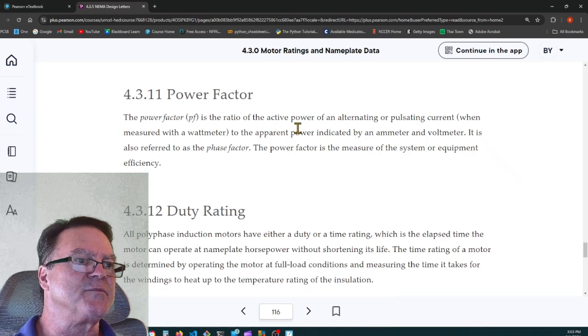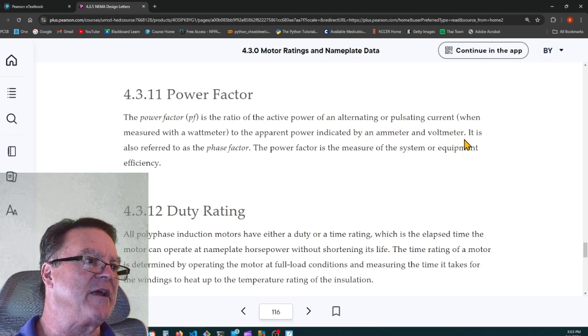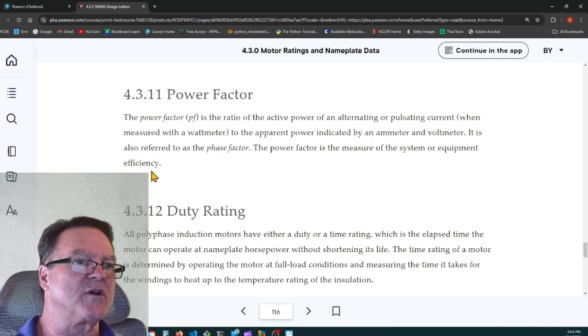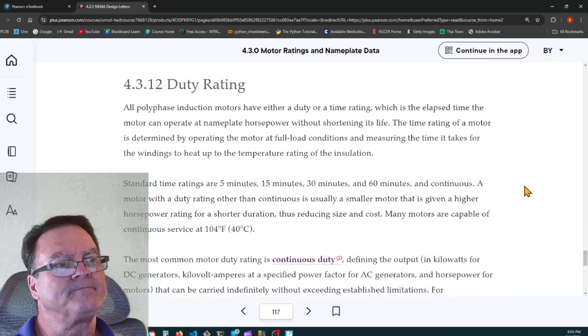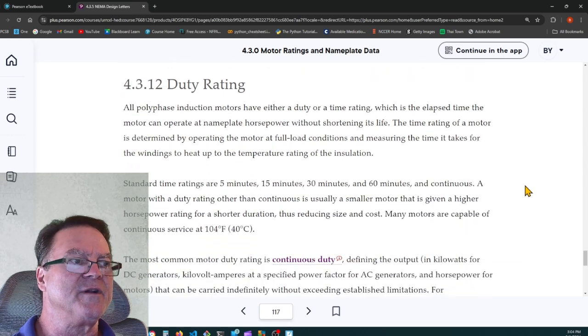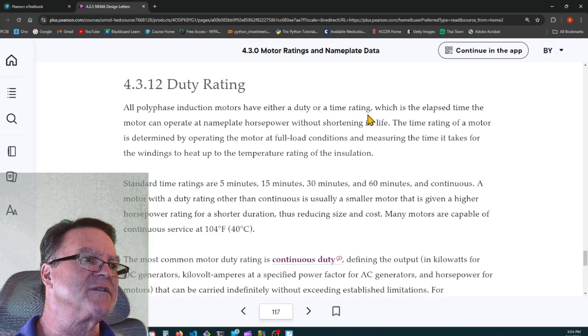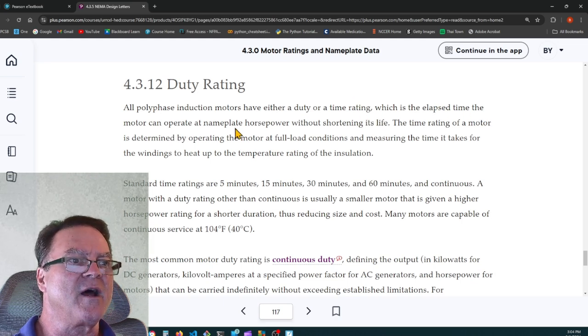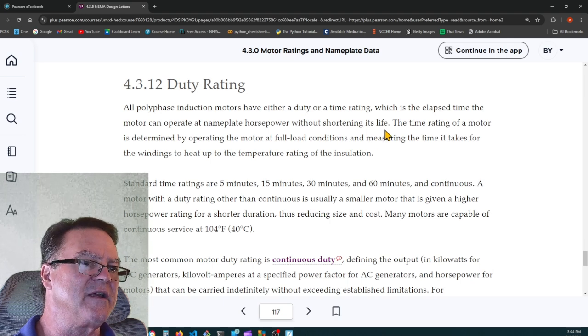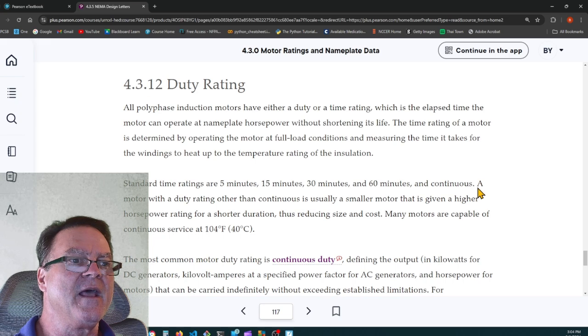Power factor. It's the ratio of active power of an alternating or pulsating current to the apparent power indicated by an ammeter and voltmeter. It's also referred to as the phase factor. Power factor is a measure of the system or equipment efficiency. And here you go, here's your duty rating. All polyphase induction motors have either a duty or a time rating, which is the elapsed time the motor can operate at nameplate horsepower without shortening its life. Standard time ratings are 5 minutes, 15 minutes, 30 minutes, 60 minutes, and continuous.